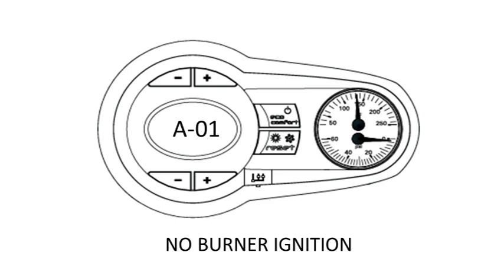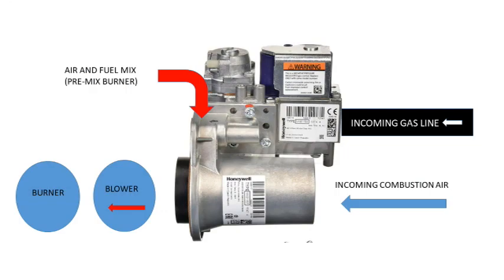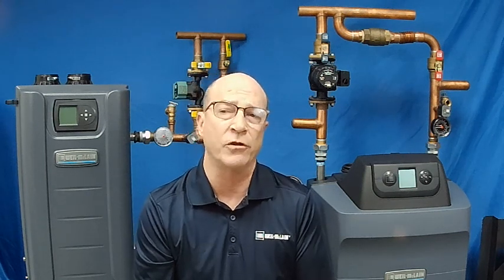Getting to the bottom of the issue will basically be the same for all of them. All of these boilers utilize negative pressure regulated gas valves. If you were to put a manometer on the manifold side of the gas valve, you will see a negative value when the valve opens. This type of system actually pulls the fuel out of the gas line, rather than depending on the positive pressure from the line. So they are diagnosed differently than the standard type of gas valve most of you are used to dealing with, where you would expect to see 3.5 inches water column positive pressure on the manifold side.